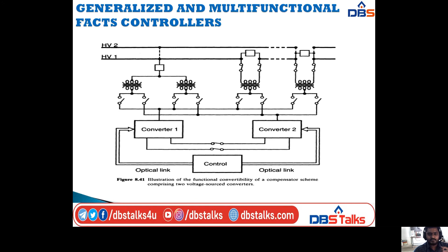By the inspection of this diagram, the figure shows the appropriate closing and opening of the circuit switches. So in the previous diagram we have so many switches. With the appropriate opening and closing of the circuit switches, connecting the converter outputs to the coupling transformers, the two converters each with 1 per unit VA rating could be configured to function as first one STATCOM.